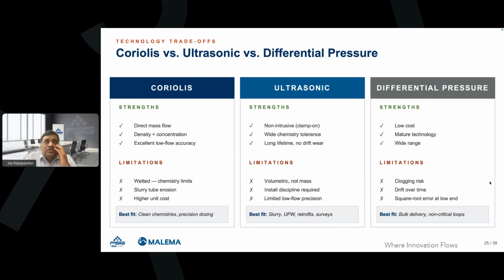Ultrasonic, this is the widely used technology in the market for chemistries as well as slurry. Non-intrusive is obviously a very high strength for this product. Wide chemistry tolerances, long lifetime, no drift, wear, and very repeatable, which I have not listed here, extremely repeatable technology. Volumetric, obviously, it cannot measure mass, so it has to be fine-tuned for different chemistries. That's one limitation, but always it can be applied for a wide range of chemistries.